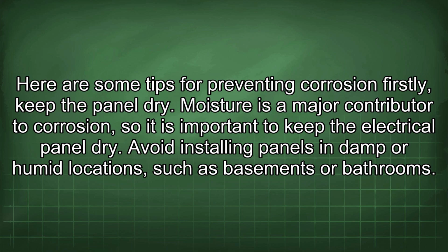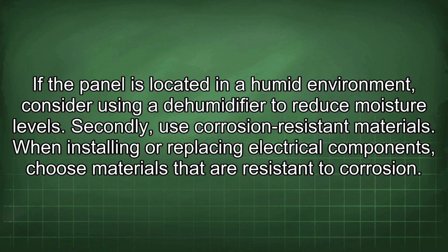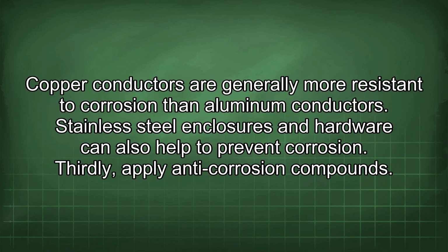Avoid installing panels in damp or humid locations, such as basements or bathrooms. If the panel is located in a humid environment, consider using a dehumidifier to reduce moisture levels. Secondly, use corrosion-resistant materials. When installing or replacing electrical components, choose materials that are resistant to corrosion. Copper conductors are generally more resistant to corrosion than aluminum conductors.